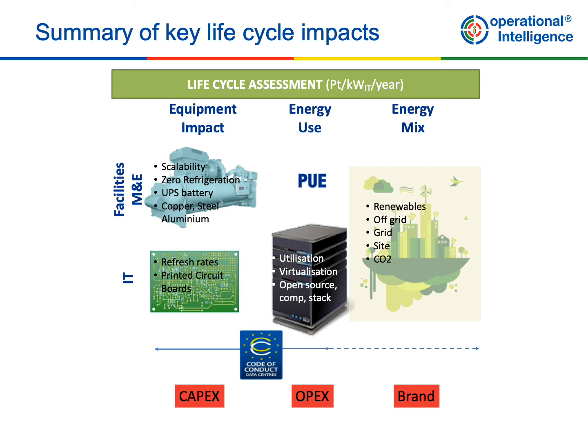We can summarise key data centre lifecycle impacts as pertaining to facilities infrastructure and IT equipment. The equipment impact of both is significant. Electronics has high impact, as do the large quantities of metal found in the installed infrastructure. There are opportunities to dematerialise through design by using zero refrigeration, for example. Energy use of IT equipment may be reduced through virtualization and increasing utilisation rates. Often there are opportunities to reduce energy consumption of cooling systems, which can be reflected in lower PUE values.